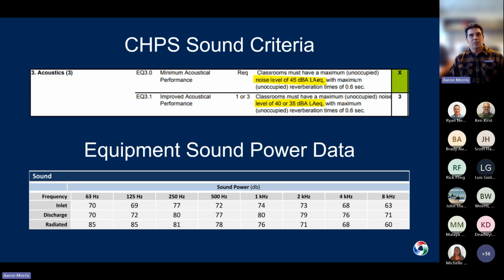So if we know our sound power levels from our basis of design equipment, and we know our goal that we're trying to achieve, the other piece we would need would be a floor plan showing where that equipment is located relative to the space and the duct path that we're designing to get from that equipment to the space. Something else to consider here: if sound is important to your project, you want to make sure that you get your sound levels for your equipment scheduled. So it's on the drawings, kind of what that basis of design is. So if you're allowing alternate equipment, they can make sure that they meet that sound requirement, or compensate with additional attenuation if needed to get the space to the sound requirement of that 45 or 35 dBA.